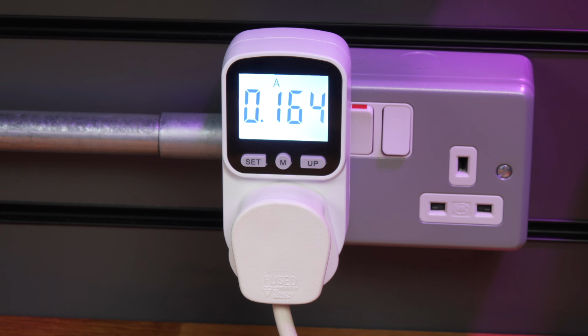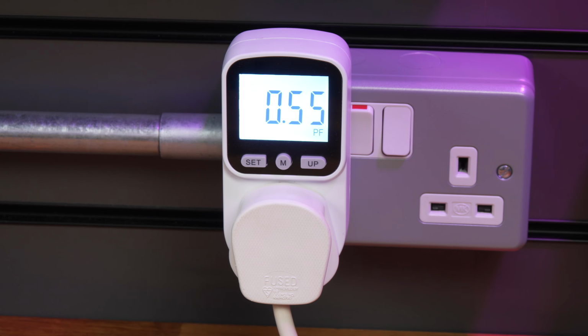So if we do the maths and multiply that voltage by that current, we get a value of 38 VA, so 38 volt amperes. As you can see, that's significantly more than the 20 odd watts that we're drawing from the wall. And if we go to the next screen on this to get the power factor, we can see we're getting a power factor of 0.55, 0.56, which explains why, because this has a very poor power factor.